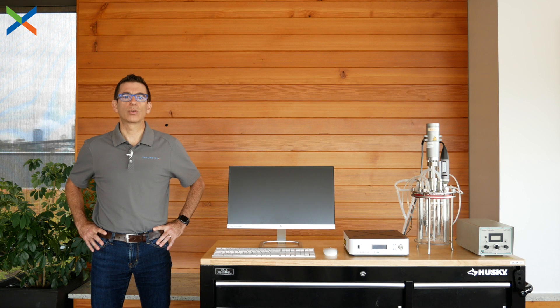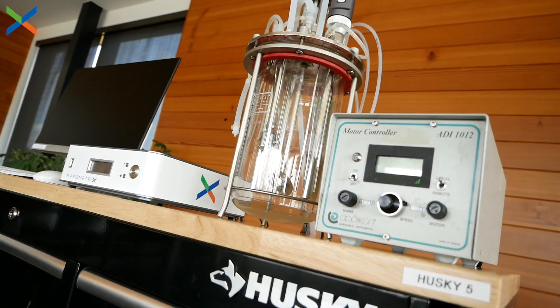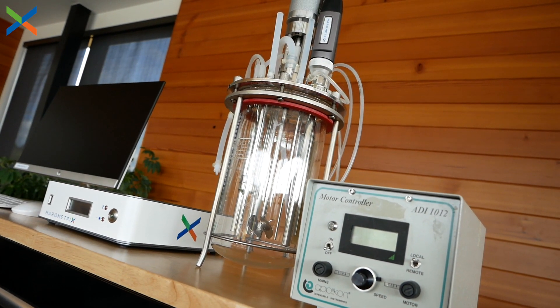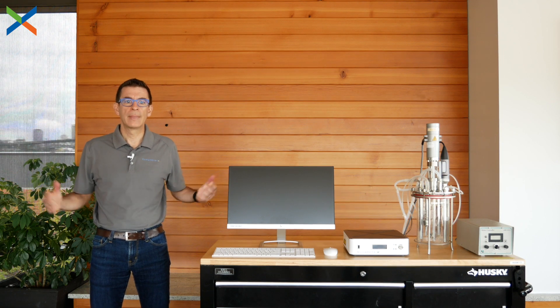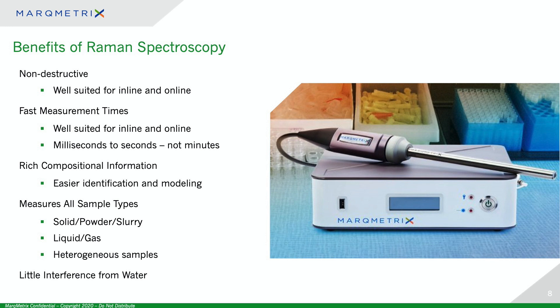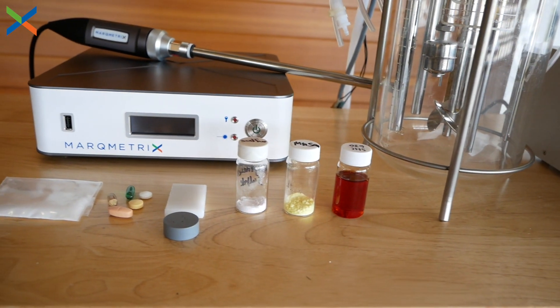The next advantage is that the Raman spectrum provides us with a lot of information about the substance being tested. Every one of the peaks in the Raman spectrum tells us something unique about what we're testing, giving us many opportunities to identify what we're looking for — which is important when measuring in a bioreactor containing many molecules of different types. There is also a direct and linear relationship between the concentration of a given substance and the intensity of the peaks in the spectrum, which means building quantitative models is easier. With a relatively small number of samples, we can build a model that accurately predicts concentration across our range of detection. We can also measure substances in all forms, whether they're solid, liquid, gas, powder, or slurry.